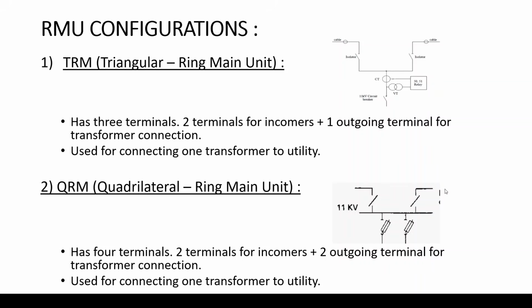Therefore, as you see here, an RMU is a sort of modular or contained switchgear having two incomers and two outgoings, or two incomers and one outgoing. The incomers can be disconnecting switches, manual disconnecting switches, or in most cases motorized breakers. This enables remote control of the RMU from the central utility office via what is called an RTU, remote terminal unit. So usually each project has a motorized breaker, which can be controlled from a central location in the utility company, therefore enabling opening and closing them in the case of any fault or any reason. For whatever reason, they can have remote control over them in order to provide the required functionality.